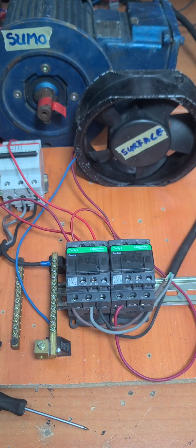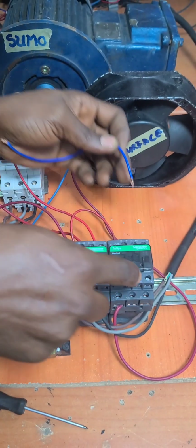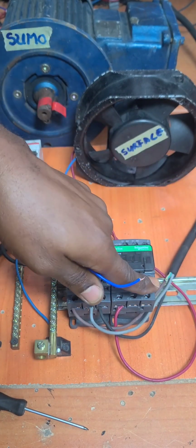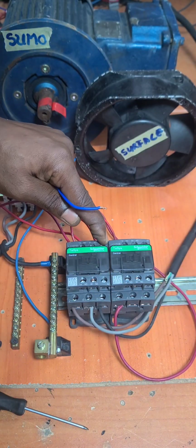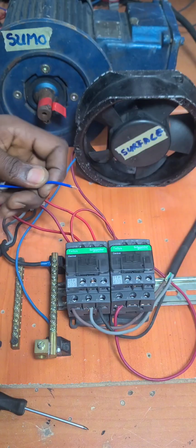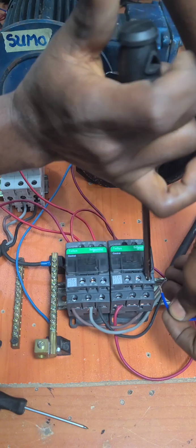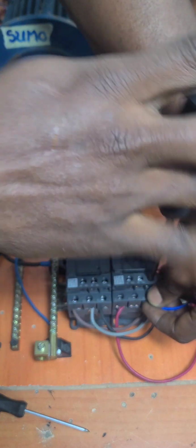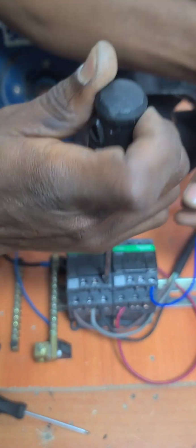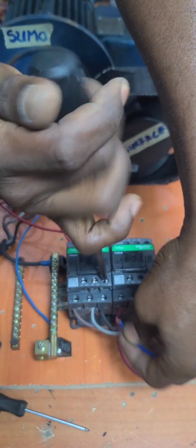So the next thing to do is to go to our A2 terminals of our contactor. So this is our A1 and this is our A2 for this particular contactor. This is our A1 and this is our A2. So we could take this our A2 from here. So we'll take our A2, slack on this, insert our wire, and then lock it up. And then we'll slack out on this one also, which is our A2, insert this wire.